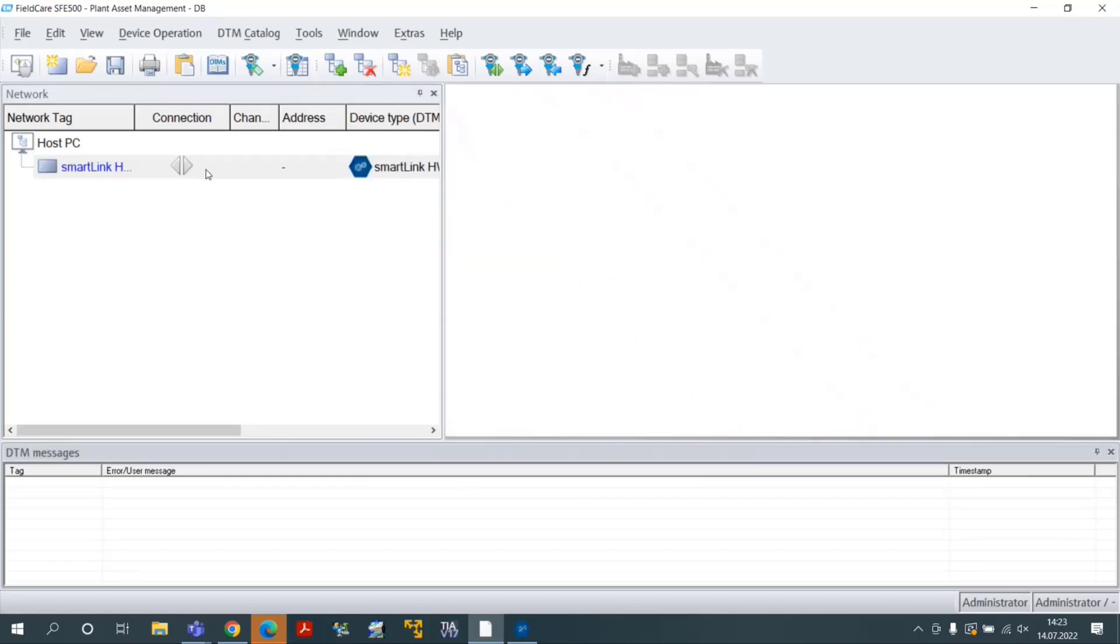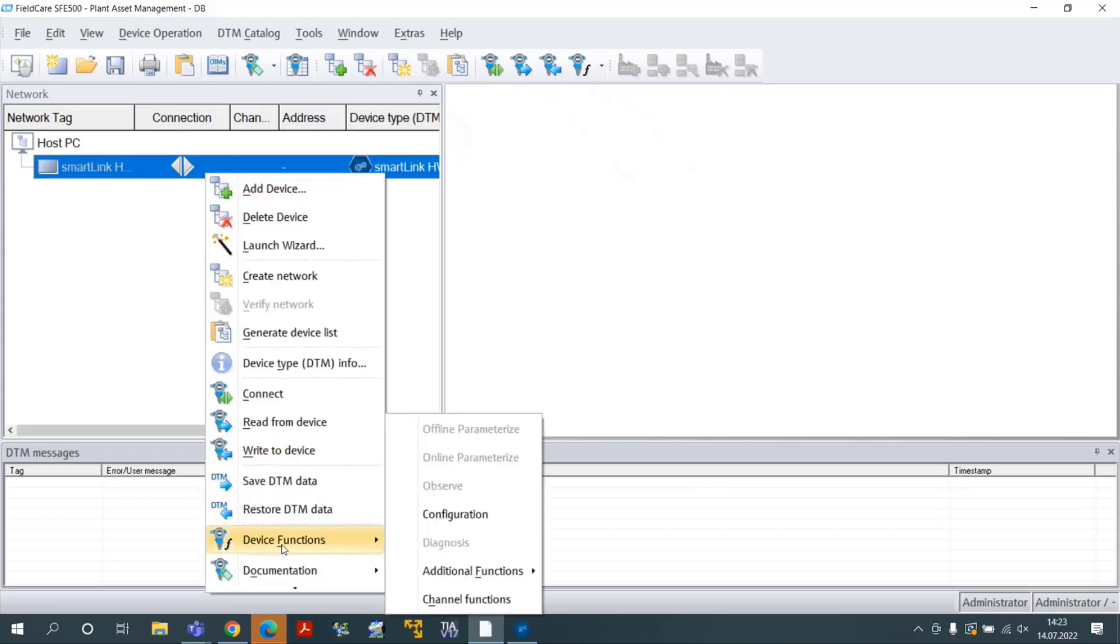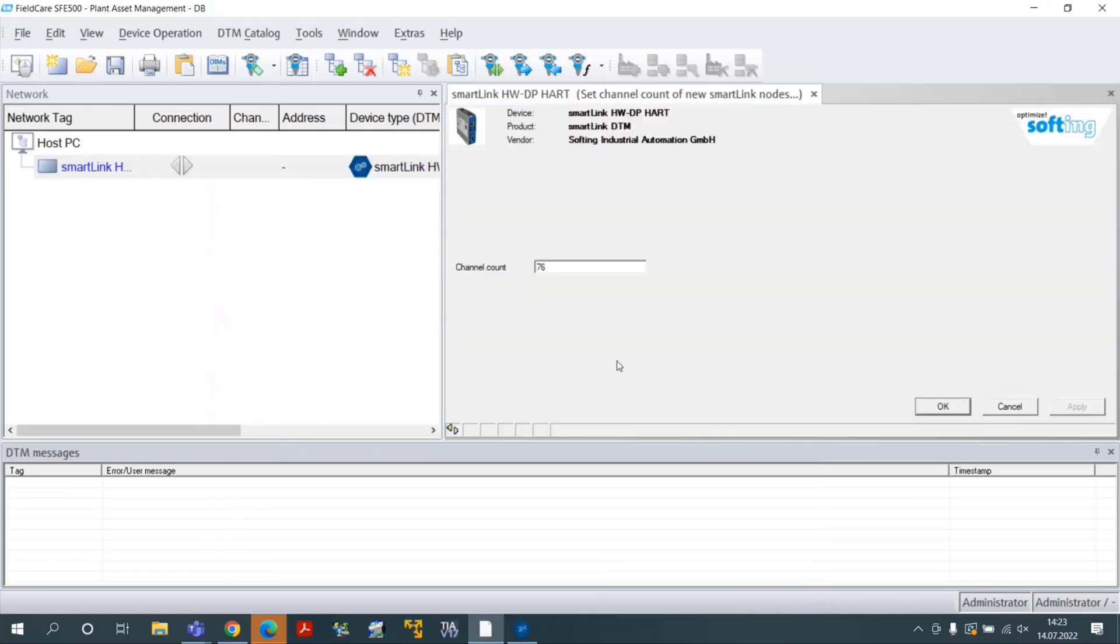Select the menu Device Functions, Additional Functions, Set Channel Count of New SmartLink Nodes. The parameter Channel Count corresponds to the amount of connected HART field devices. Updating this parameter to the correct value will decrease the scanning time.